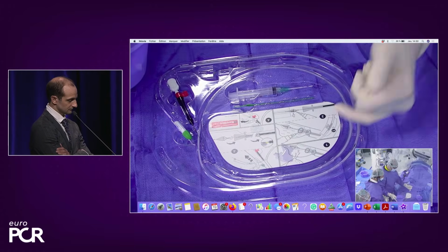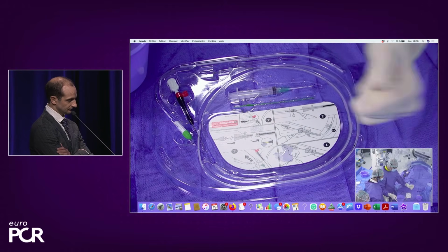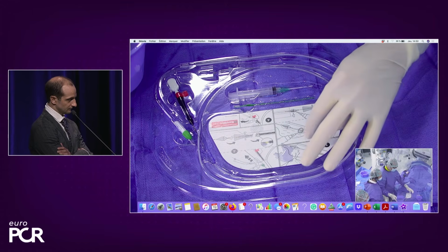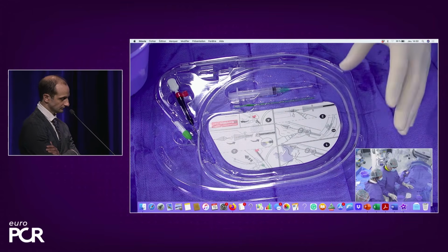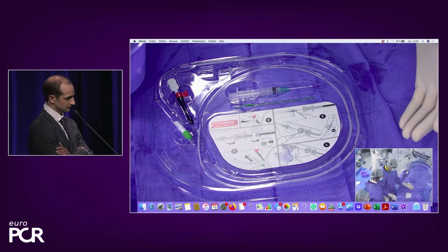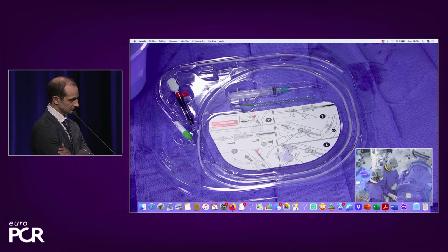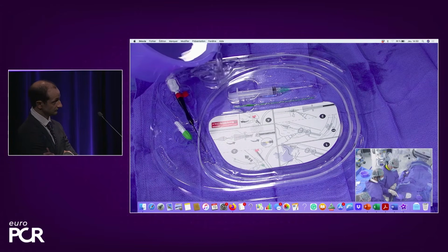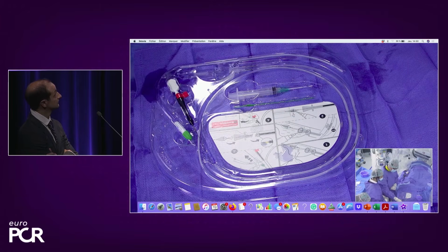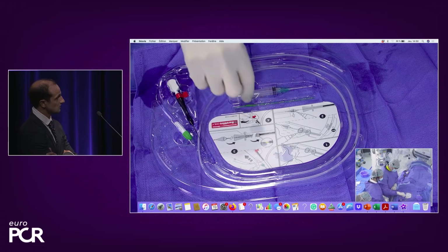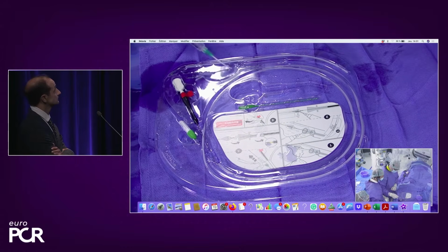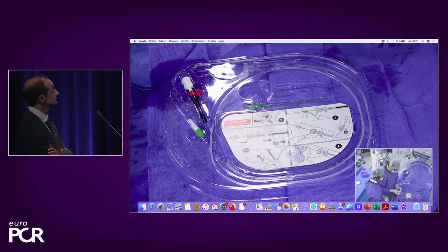You have to follow the screen, and there are 4 different steps. The first one is to flush and to remove the bubbles from the filter, and then to load the filter. You put the saline, heparin saline, in the box, and then you have a little syringe, and you will purge every bubble from the device, from the filter.